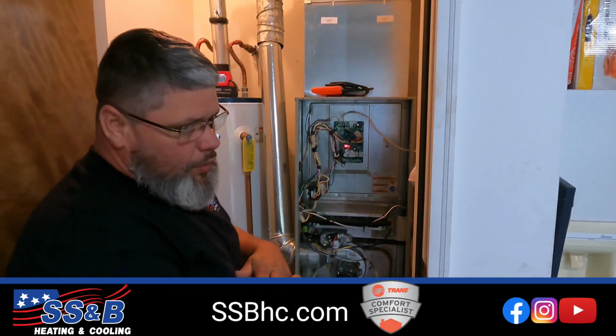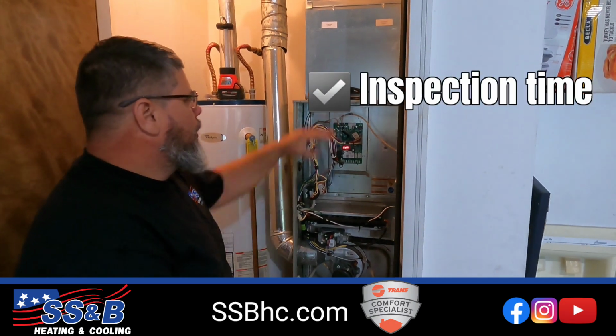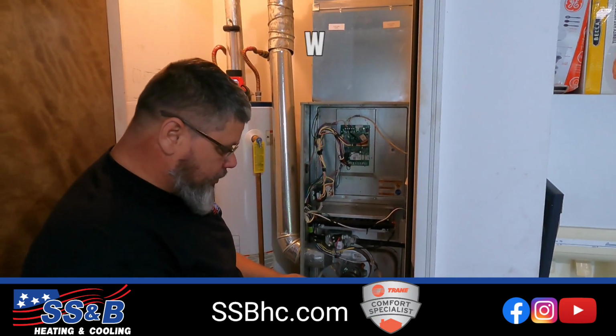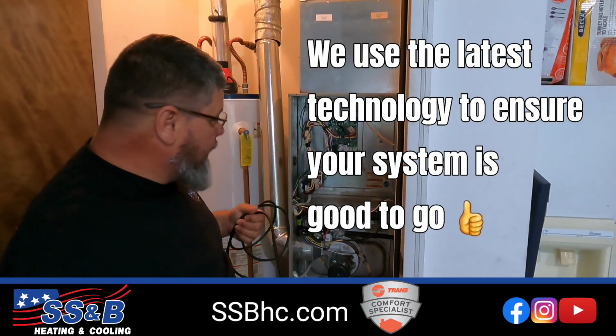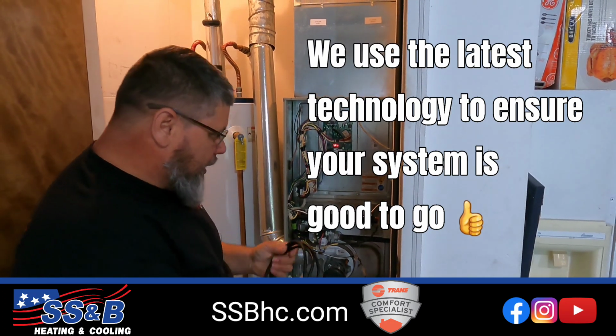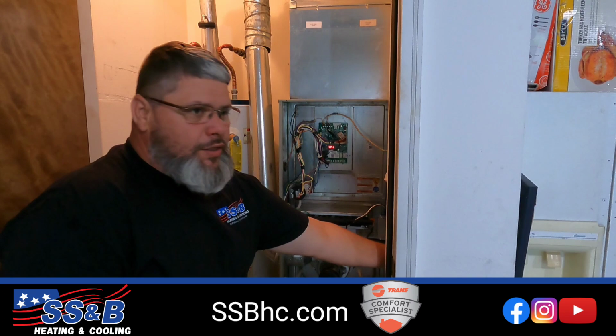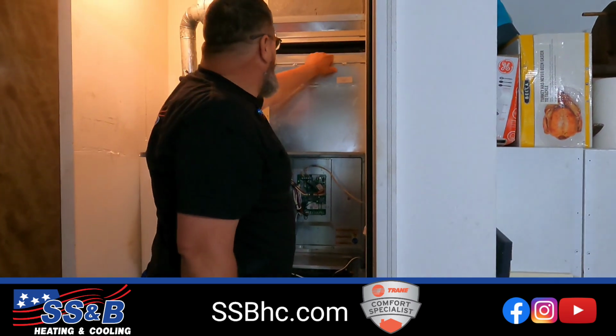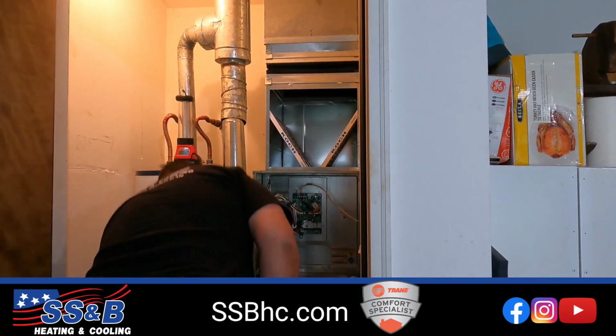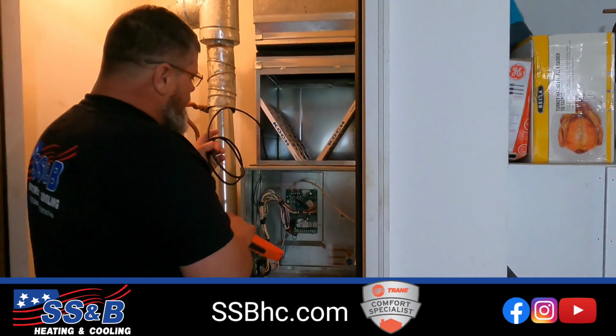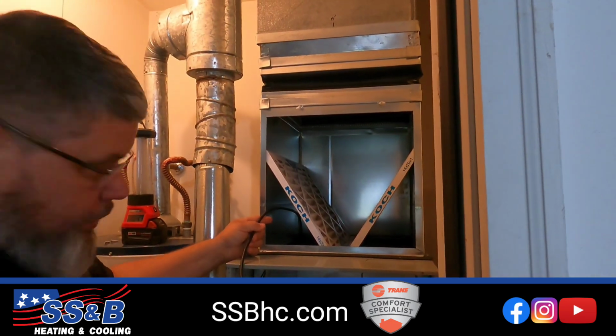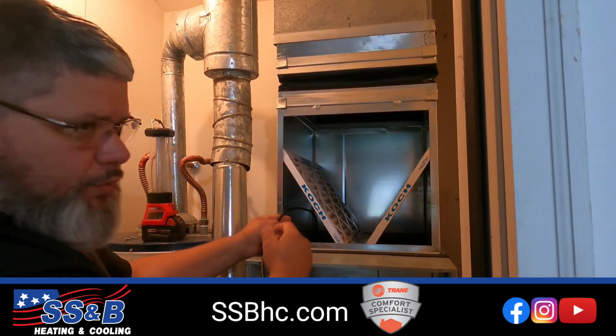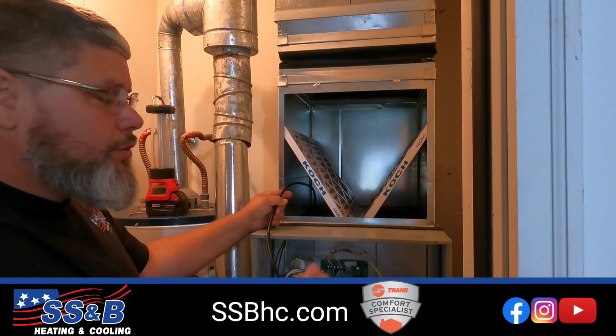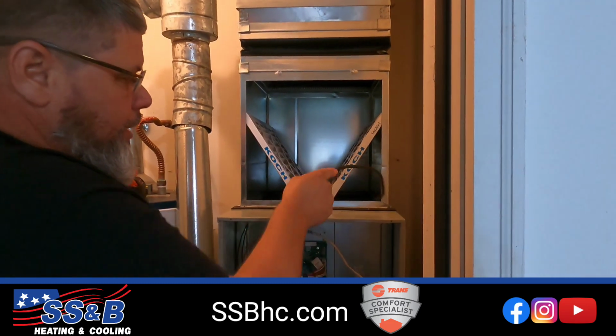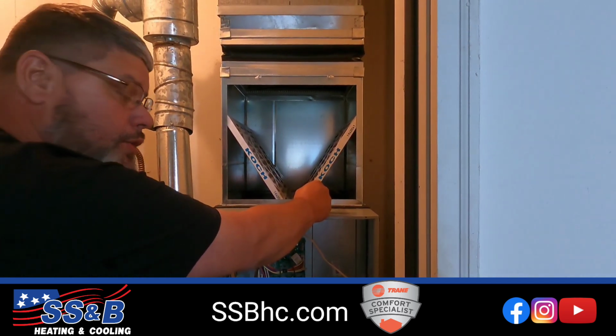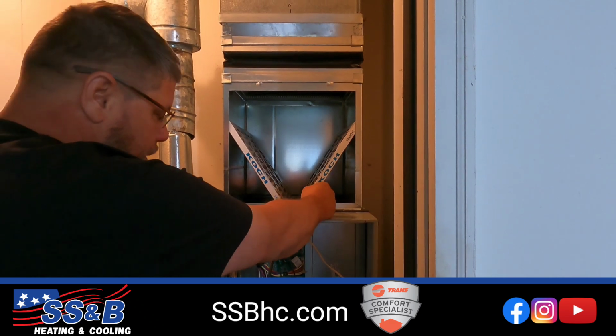When this cycles down, then we'll start doing our inspection of our evaporator coil and of our blower, and we'll use a video scope. It gives us access to a lot of places that you can't normally get to without taking it completely apart. So once it cycles down, we can actually shut off the power. At that point, we can actually go in and check your blower, which is what moves the air through the system. We check it for the amp rating on the blower motor, and then we also can check on the other side so that we can actually see if there is any dirt or dust that might need additional cleaning. At that point, we can actually decide.